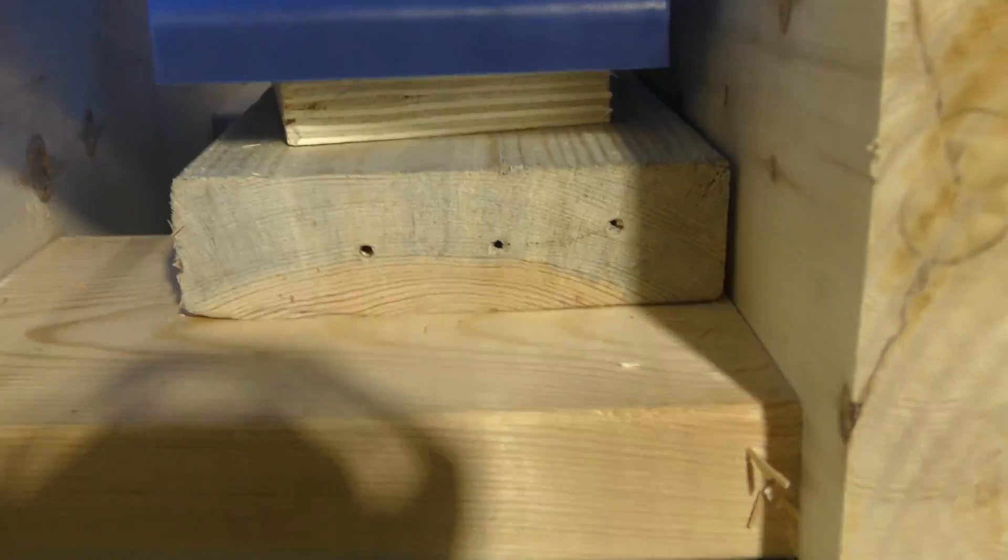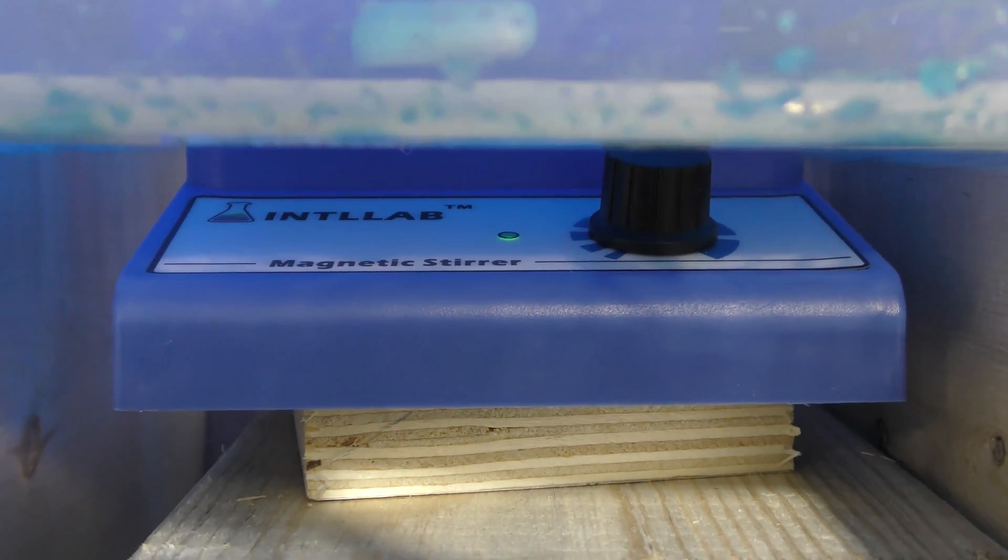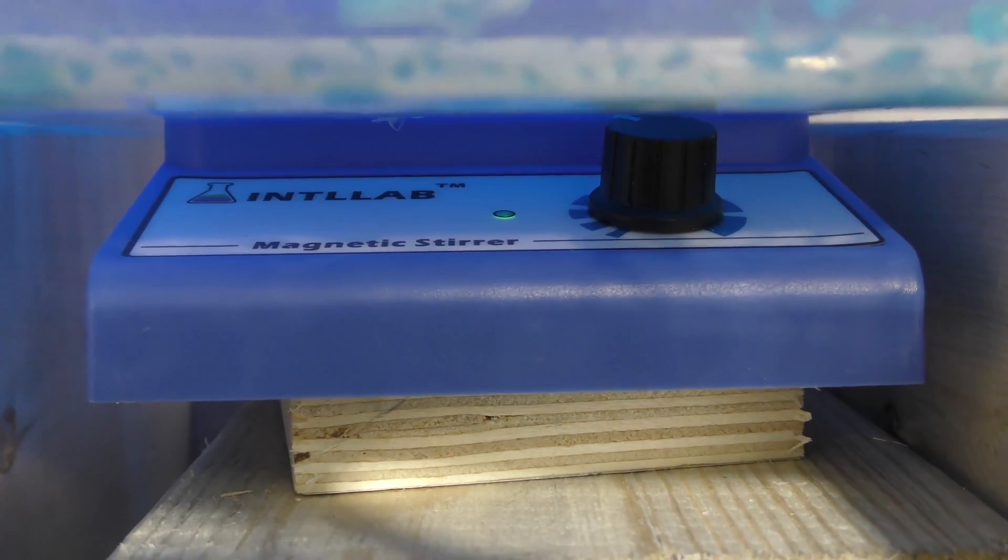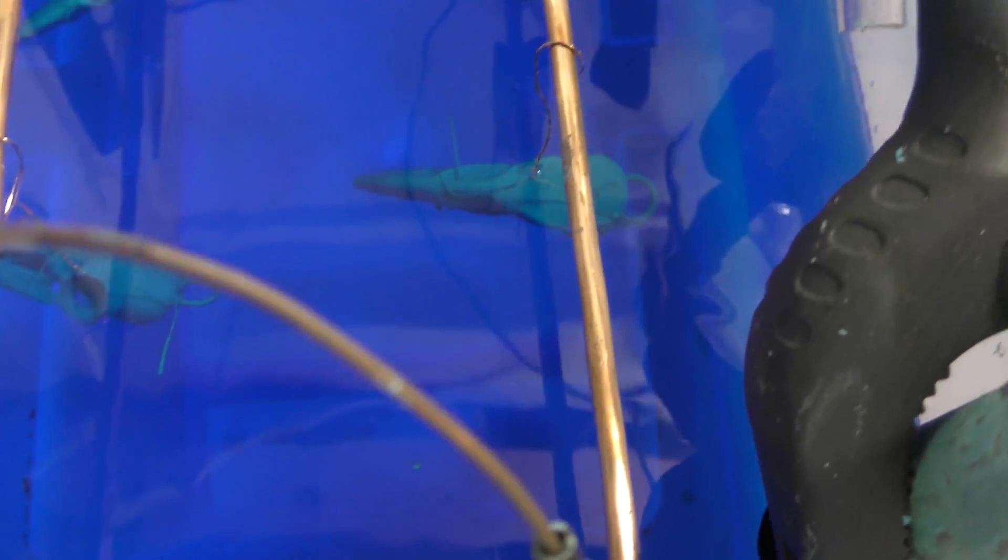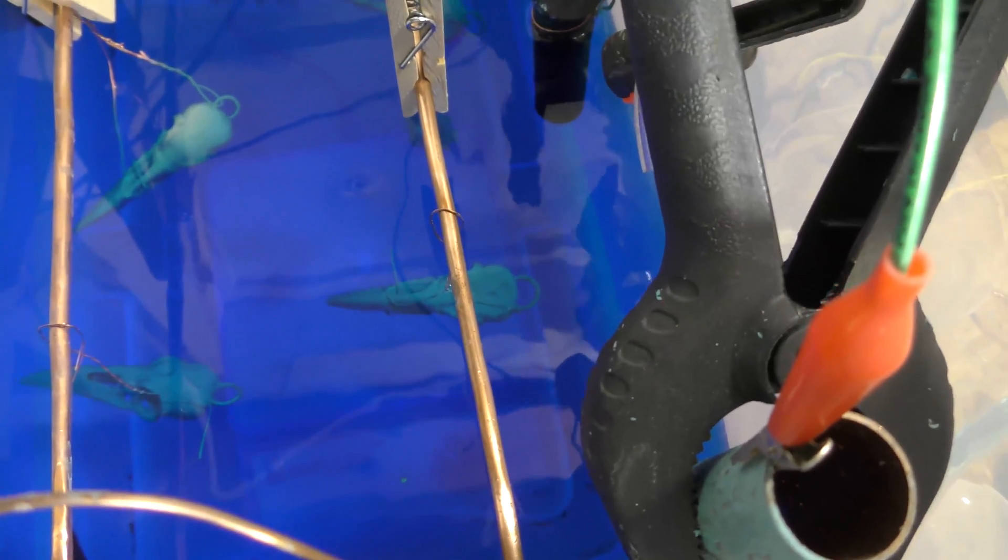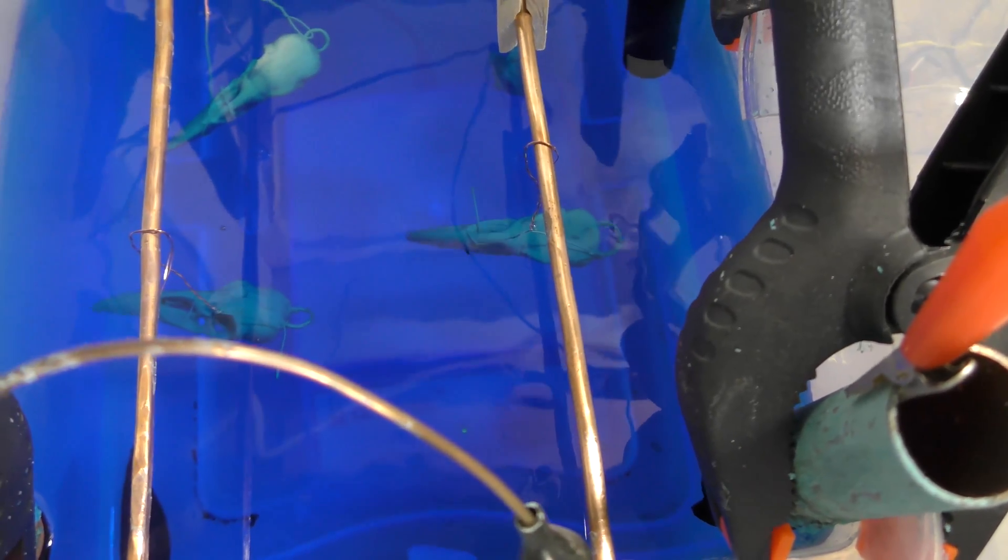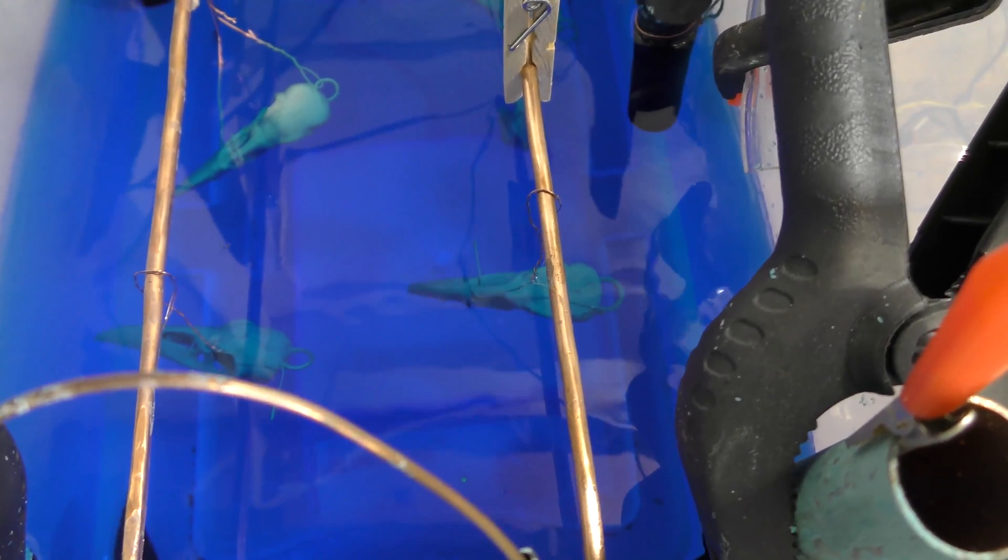So let's go to the last one I would ever buy. This is the INTLLAB Magnetic Stirrer. And I'll put a link below on the one that may be not to buy. It will not run a two inch pill. It only runs the pill it came with. And that's it. So if you try to put a different pill in there, like a different shape pill or different size pill, it will fail. And that's because of the spacing of the magnet.